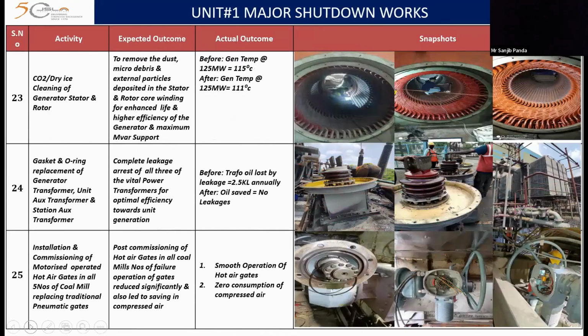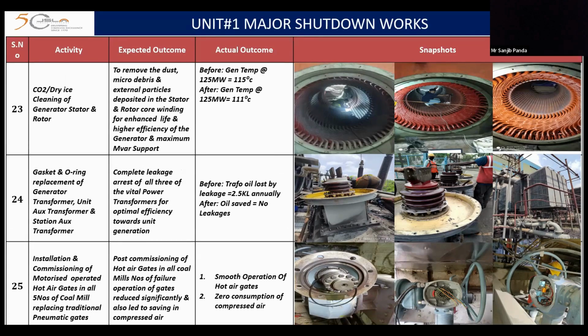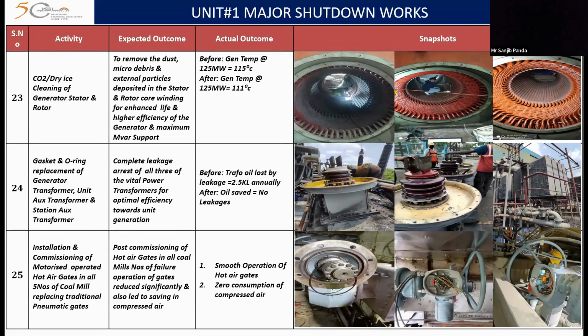CO2 or dry ice cleaning of generator stator and rotor has been done as a best practice to remove the dust and micro debris, which in a conventional way are very difficult to be removed. Gasket and O-ring replacement of generator transformer, unit auxiliary transformer and station auxiliary transformer has been done to arrest the leakages completely. Installation and commissioning of motorized operated hot air gates in all 5 numbers of coal mills has been done by replacing traditional pneumatic gates.